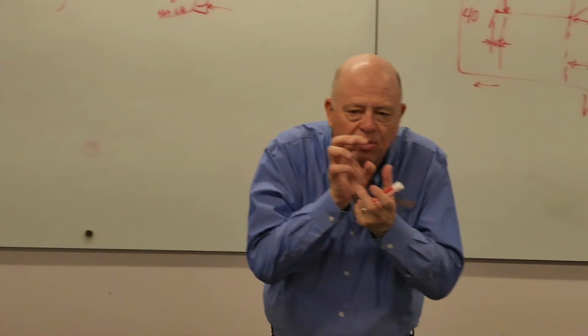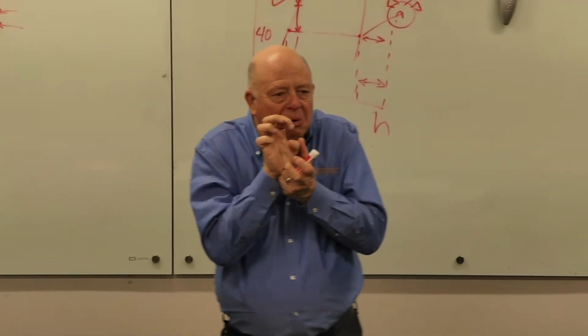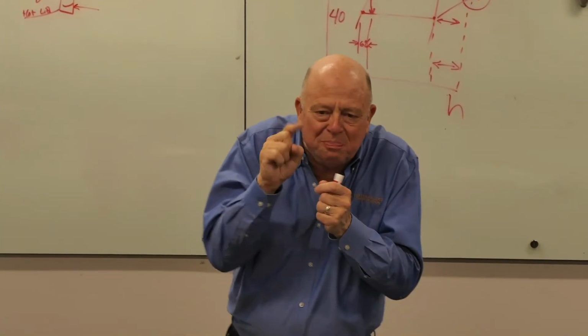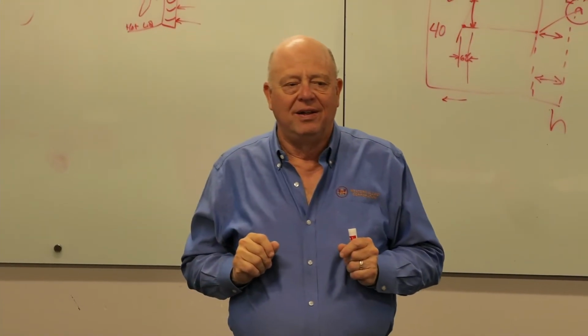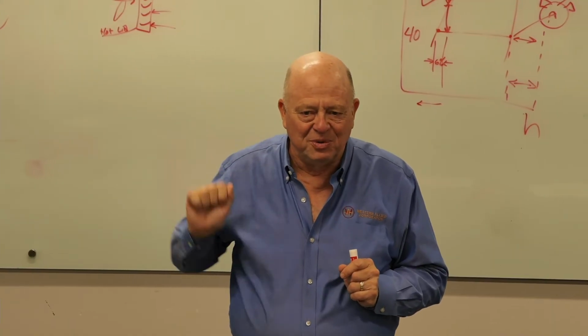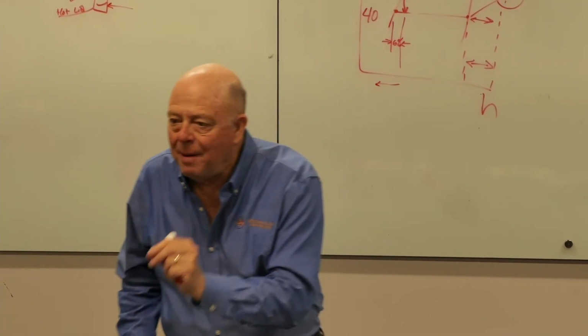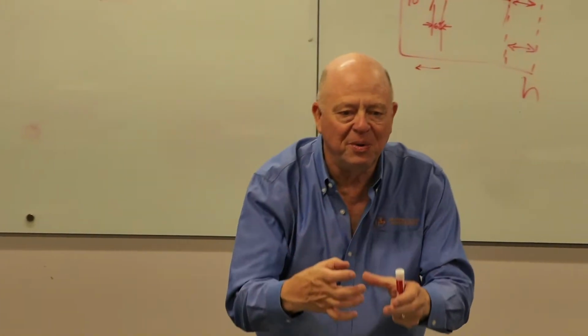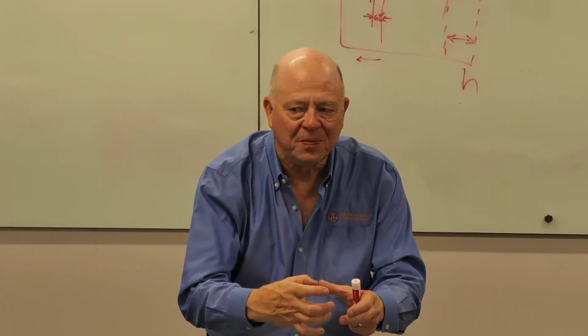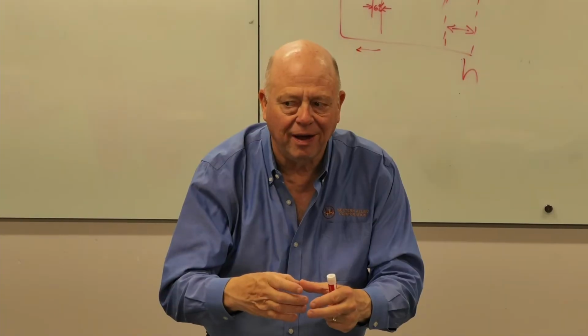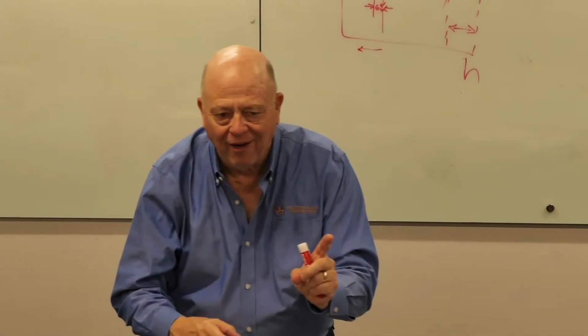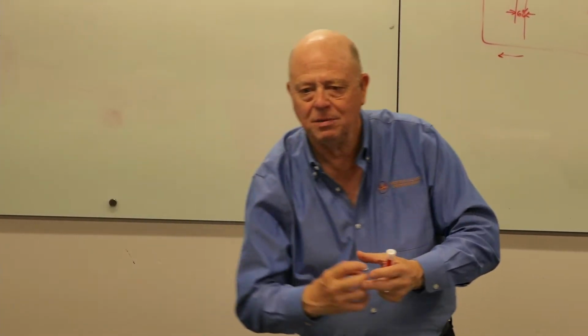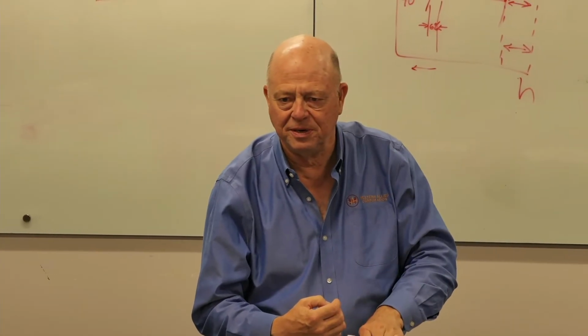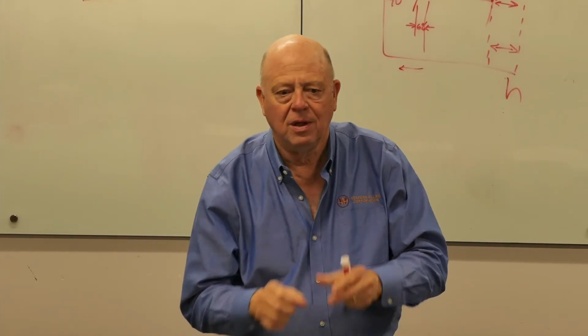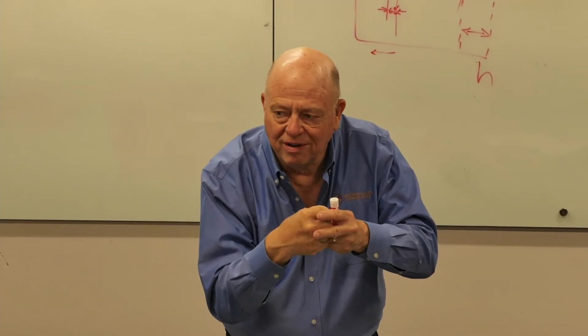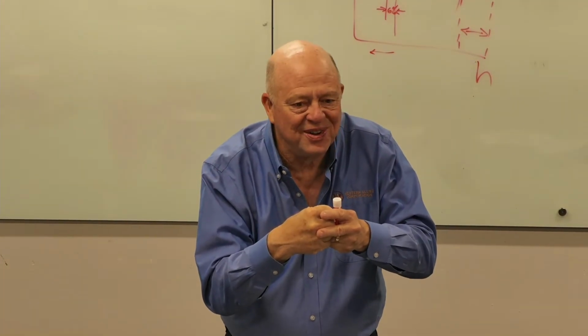They put the very minimum amount of copper and the very minimum amount just to get it to spin and move some air. They weren't designed for variable speed. This is what happens when you variable speed a motor. It ramps up and down. It ramps up and down. But what happens to the available torque as it goes down in speed? Less. What happens to the friction? It doesn't go down as fast.